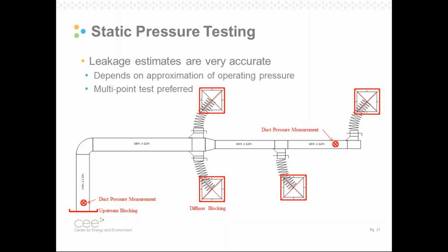We spent a lot of time learning how to make good measurements, and at the end of the day, we ultimately settled on the tried and true static pressure test. This method is very accurate when done right, and it's fairly simple to do right. Most important thing is that when we do this test, we measure duct leakage at a representative operating pressure. So this often requires us to measure the pressure beforehand. And it's even better to take what we call a multi-point test, where we test the duct leakage over multiple pressures. This lets us produce what we call a characteristic curve for that duct section, and that really enables us to understand how it will leak over a variety of pressures, pre and post sealing.